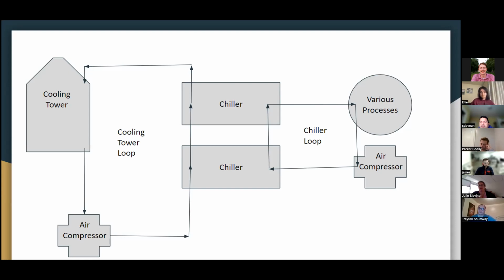Generally in this case, Sunny, it's pure speculation because we're working with people who have just inherited the building. So probably not a lot of historical information is going to be super valid. Okay. And you have the nameplate of the air compressor? Yeah. So the first thing to do is check whether that air compressor can run with cooling tower water, which will roughly be 65 to 75 degrees, versus chilled water, which is probably 45 to 50 degrees. Because if that air compressor was perfectly matched to run with 50-degree water, then again you come back to the feasibility versus energy savings issue, because that might mean, hey, we've got to retune this whole air compressor or buy new. They may have special ordered that air compressor to run with chilled water.